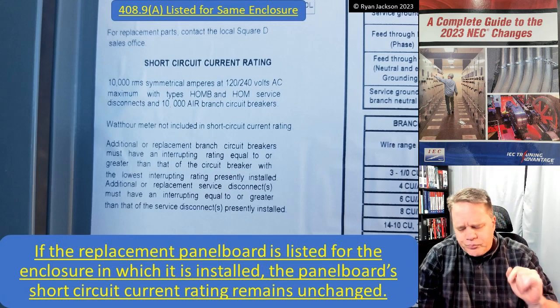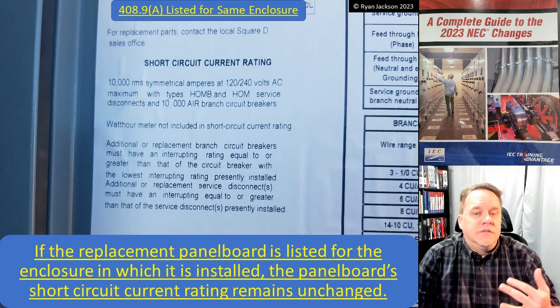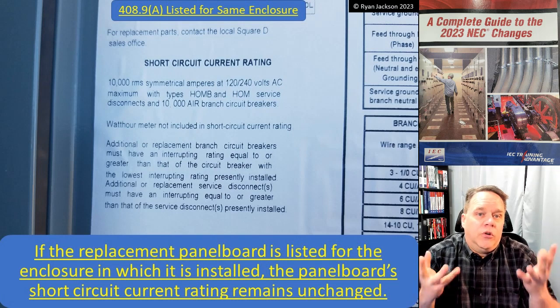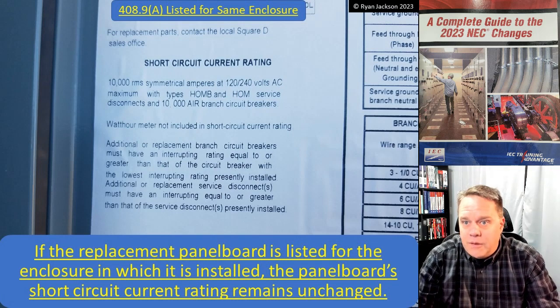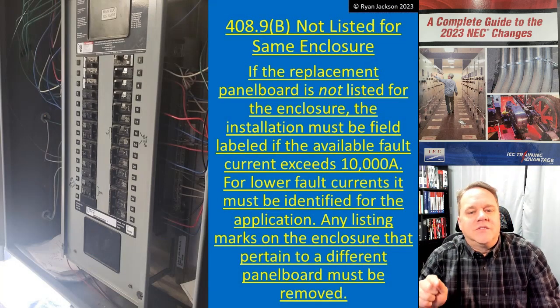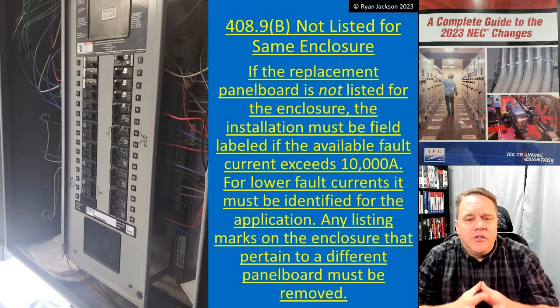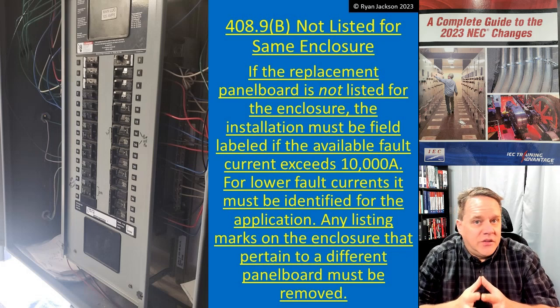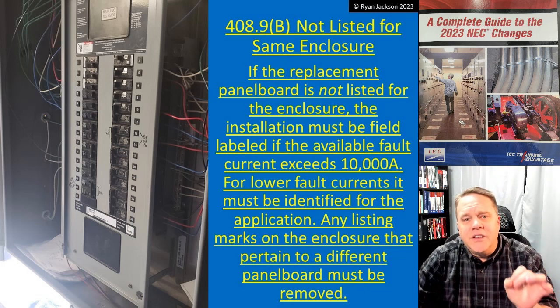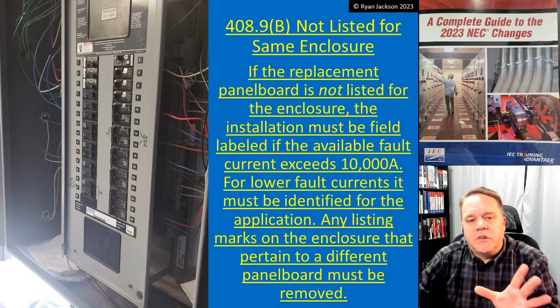Looking at this photograph, it says 10,000 RMS symmetrical at 120/240 — that is the short circuit current rating. The short circuit current rating is the amount of current that a piece of equipment can withstand without extensive damage. Quite frankly, how much current can this panelboard withstand without blowing up — that's what we're talking about. If the replacement panelboard is not listed for the enclosure, the installation has to be field labeled if the available fault current exceeds 10,000 amps. For lower fault currents, it must be identified for the application, and any listing marks on the enclosure pertaining to a different panelboard must be removed.